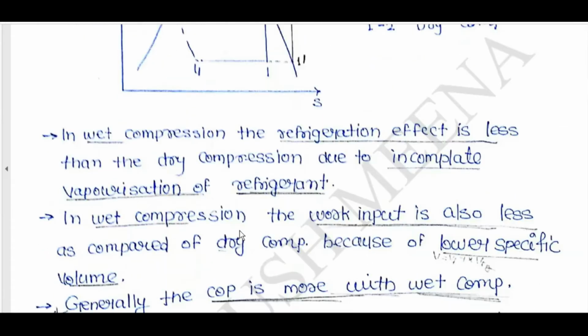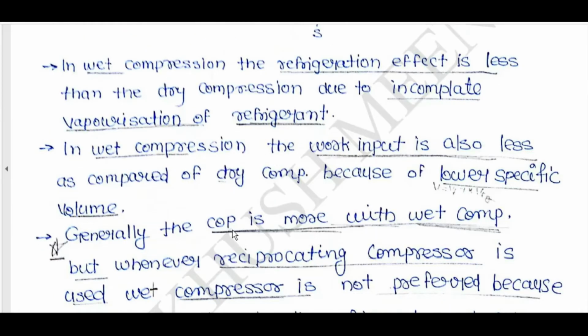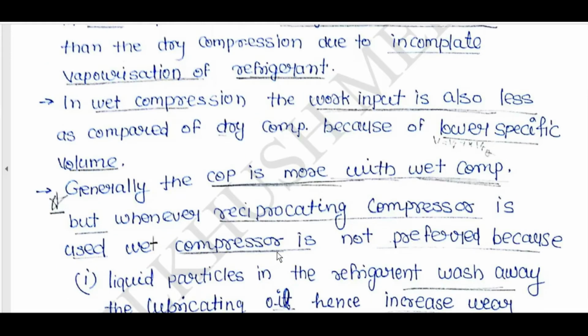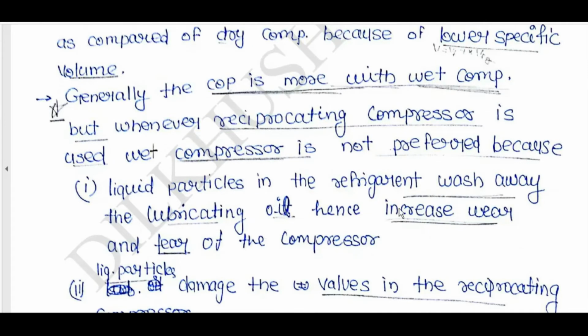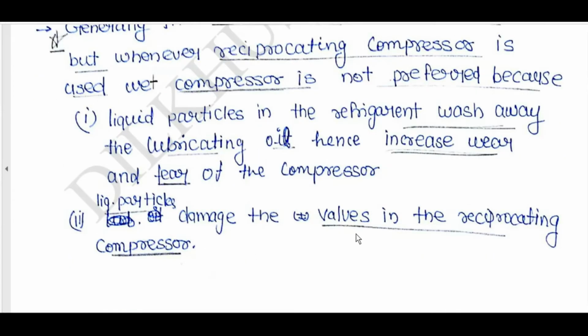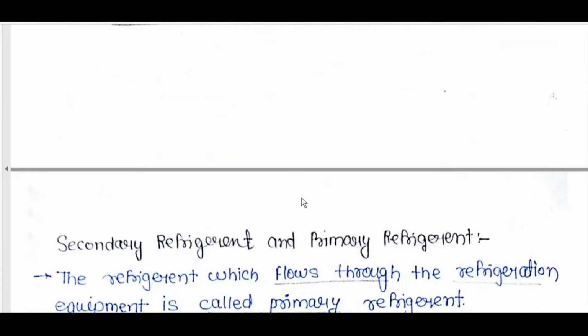Generally, COP is more with wet compression, but whenever a reciprocating compressor is used, wet compression is not preferred, because liquid particles in the refrigerant wash away lubricant oil, hence increasing wear and tear of the compressor. Liquid particles damage the valves in a reciprocating compressor.